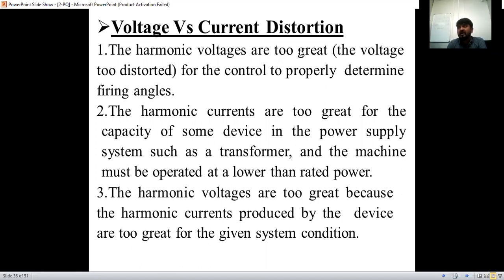If there is current distortion, it means there is a spike in the current, so high current will be applied. We check the rating of the device, whether it gets damaged, and how it sustains that. So through practical tests, we intentionally create harmonics to test the devices.